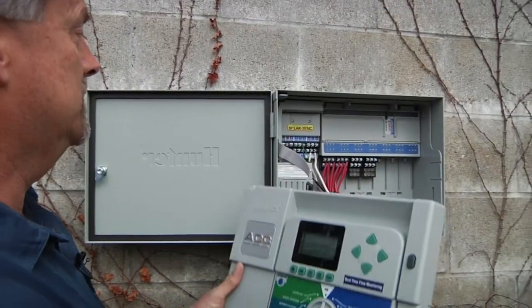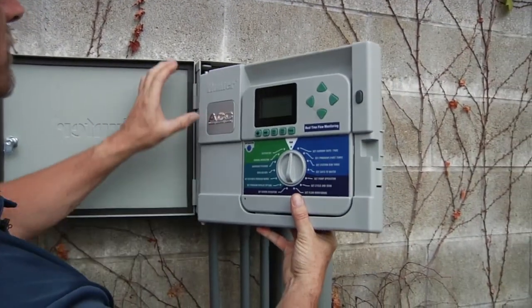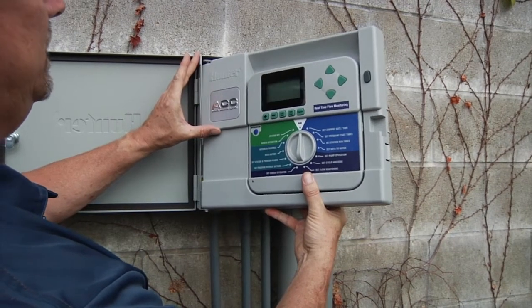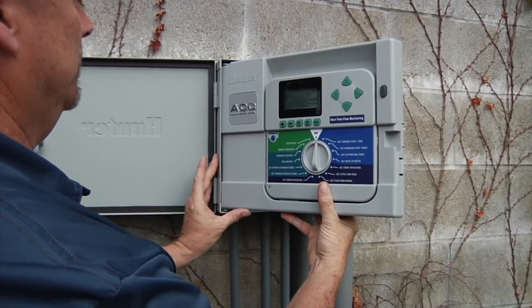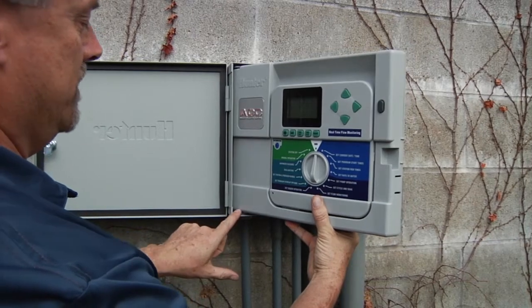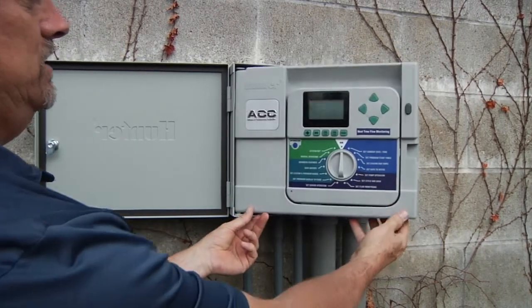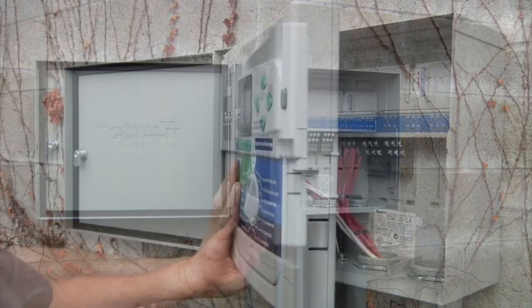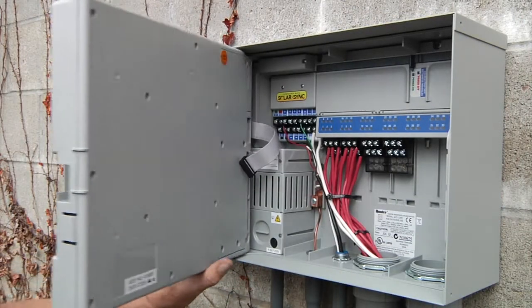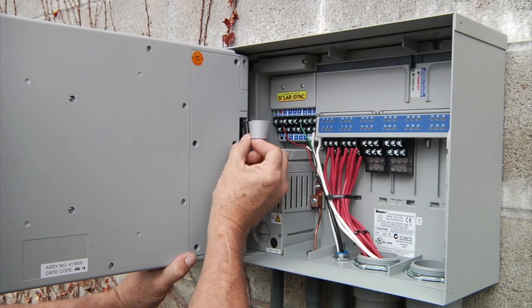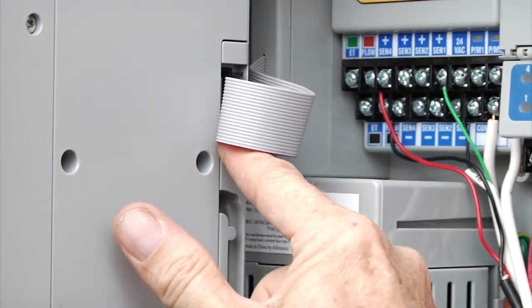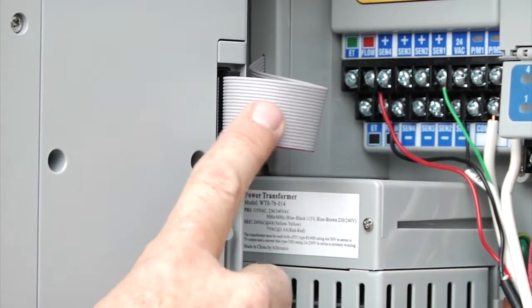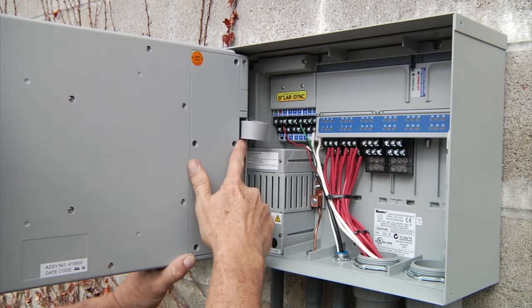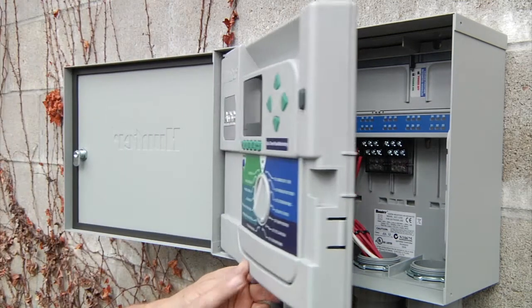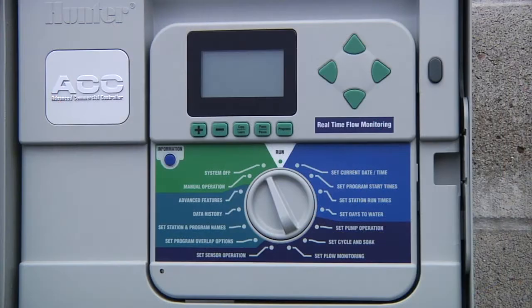So to install the inner door assembly onto the hinges, it has an upper and lower hinge pin. Simply place the upper pin into the upper hole and then gently force it upwards. That'll allow the lower pin to pop into place. And once both are in place, your inner door assembly is attached. So one of the last connections to be made here is the inner gray ribbon to the inner door assembly. Ensure that you've got the power completely turned off to the controller when you make this connection. The gray ribbon is responsible for bringing power and information over to the face pack. So now we can turn the power back onto the controller.